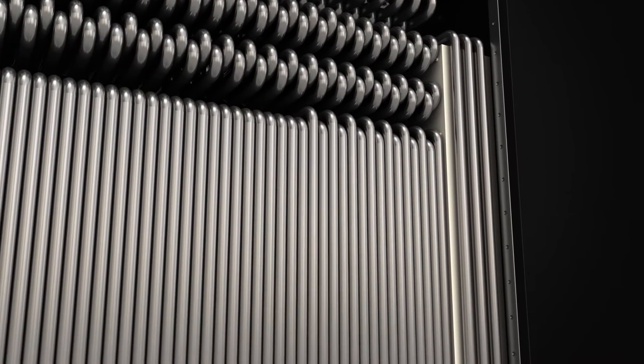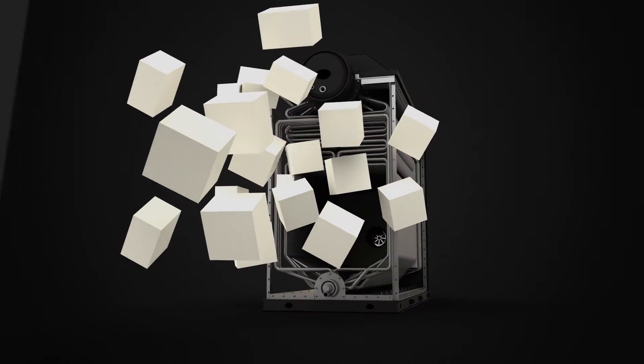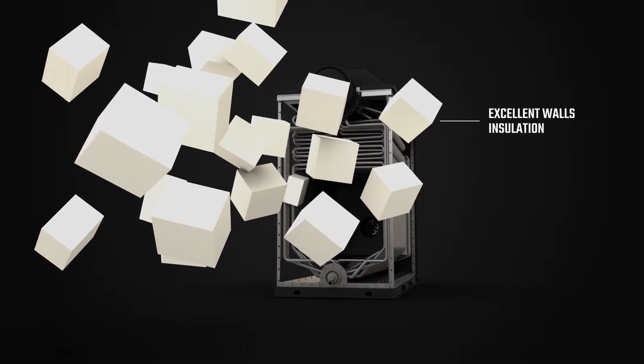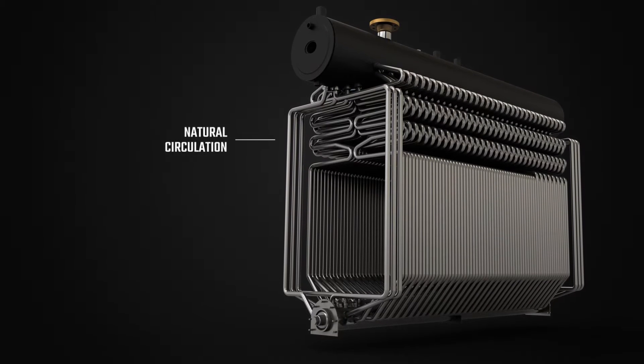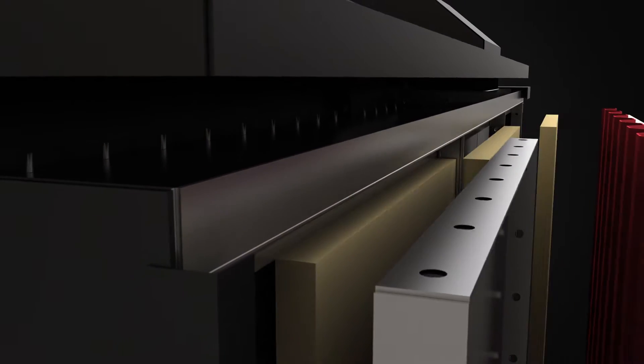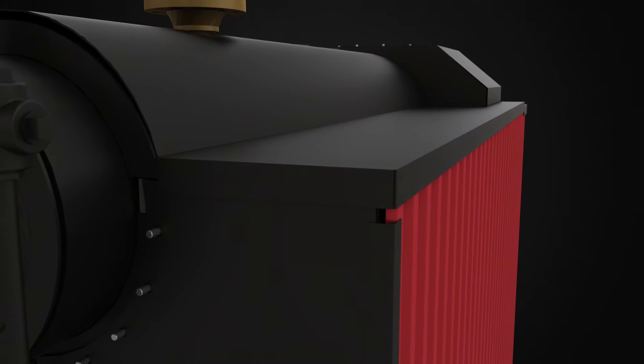The front and rear wall are made of high-temperature ceramic wool, ensuring excellent wall insulation. Downcomers are located inside the front and rear wall for natural circulation in the boiler. The internal envelope, tight against gas combustion, combined with an outer heavy steel casing, protects both the boiler and surrounding space.